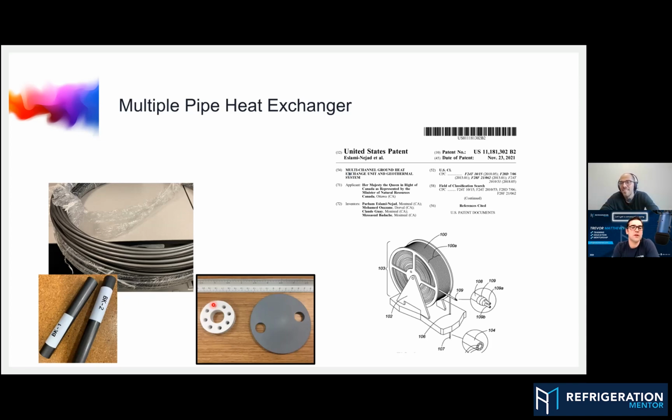Okay, because with CO2 we're working at a higher pressure. So what would the pressure be running through these pipes right now? Even with 100 bar of pressure, because you're using tiny channels, they can resist high pressure with pretty small pipes. Of course, when you need a big pipe and high pressure, this is going to be problematic, and you're not able to use plastic. But with very tiny dimensions and diameters and high pressure, it's still plastic. We have plastics, pretty small pipes, that can go up to 100 bar pressure.